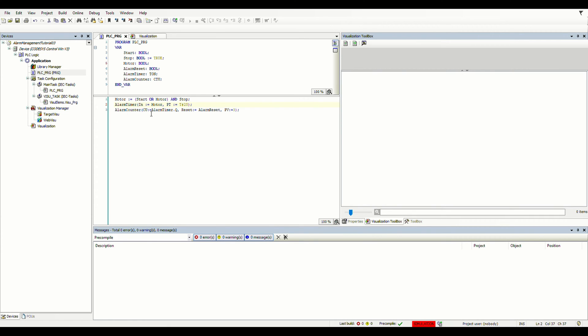The counting-up input is the alarm timer's output — the done bit of the timer — and the reset input is the alarm reset. We have the preset value as three, meaning that when the alarm in the second row happens three times or more, the done bit of the counter will become true and we will receive another alarm. So we have two alarms: one when the motor has been on for over two seconds, and another when the first alarm has happened three times or more.